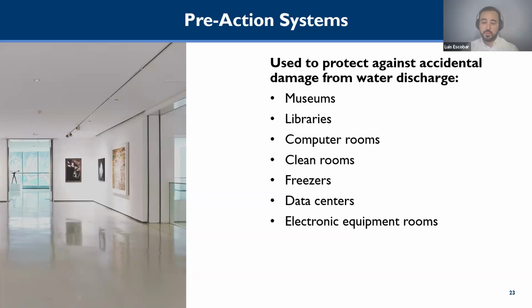The intention of this system is to control the way the water is released. Pre-action gives us an idea that something has to happen before the water is released. What happens here is we have two conditions so the water can be released. One of them is the sprinkler by itself. That's one condition. If the sprinkler is open for this system, it doesn't necessarily mean that the water will be released, because we need to meet the second condition, which could be a smoke detector activation, a heat detector, or any other means of activation. But long story short, for this system, we need to have two conditions so the water can be released, and we don't have an issue releasing water where we don't want water, right? It could be the last resort for very expensive occupancies.